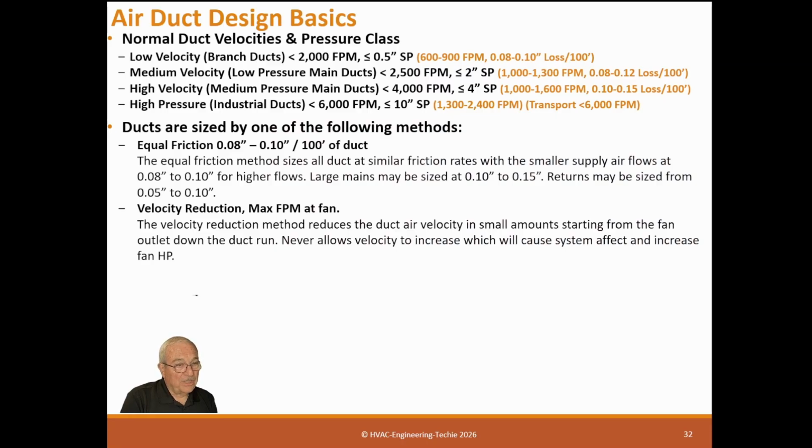air starts going down the duct, the resistance of the duct starts slowing the air down, thus decreasing the velocity but increasing the static pressure. It's called static pressure regain. And you get static pressure regain for free. Increasing velocity costs you horsepower. So all you've got to remember is don't ever do something like a fitting or something that has a lot. I will explain all this in the duct design, but it basically means it's system effect, and we don't like that. That's not good.